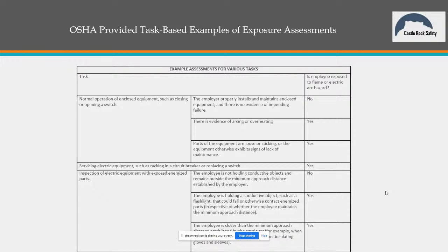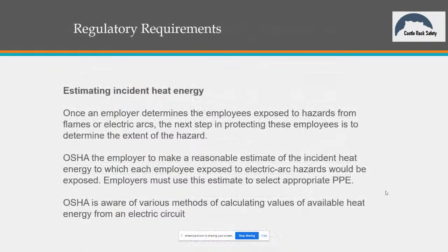And if I'm doing normal operation, servicing equipment, racking in breakers, and so forth, if I'm inspecting electrical equipment, holding a conductive object or not, and I remain outside the MAD distance, no arc flash hazard. Again, it's just a matter of what the task is. Okay. Right. I agree. So, how do you know what you're exposed to on the utility side?